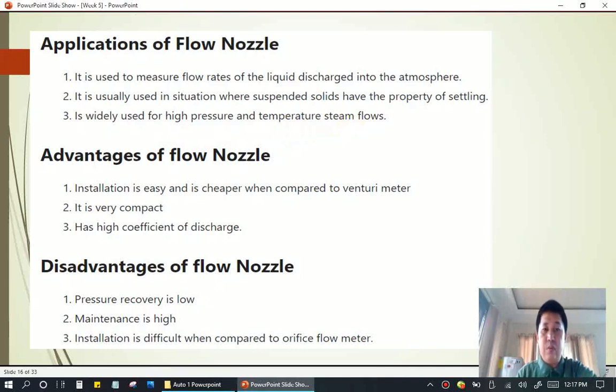So in this type of flow measuring device, we have the advantages of the flow nozzle. Installation is easy and cheaper when compared to the venturi meter. It is very compact and has a high coefficient of discharge. We also have the disadvantages of the flow nozzle. Pressure recovery is low, maintenance is high, and installation is difficult when compared to the orifice flow meter.